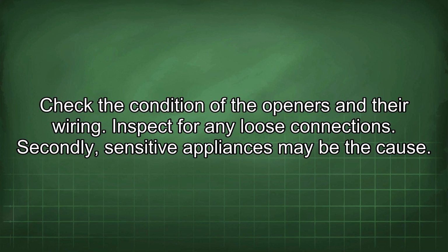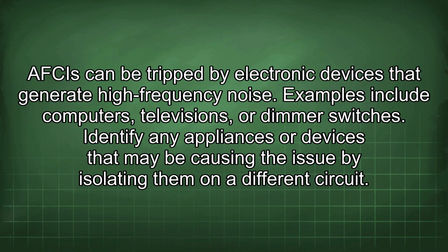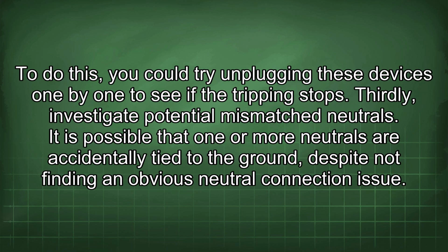Secondly, sensitive appliances may be the cause. AFCIs can be tripped by electronic devices that generate high-frequency noise. Examples include computers, televisions, or dimmer switches. Identify any appliances or devices that may be causing the issue by isolating them on a different circuit. To do this, you could try unplugging these devices one by one to see if the tripping stops.